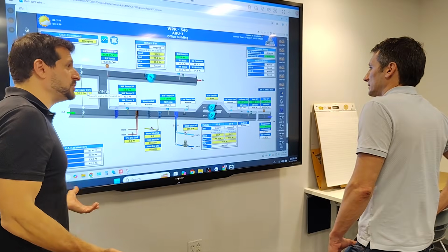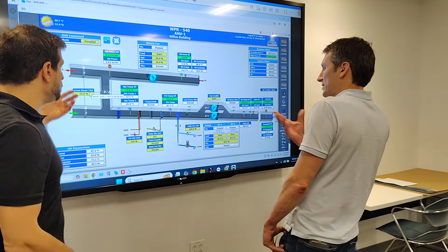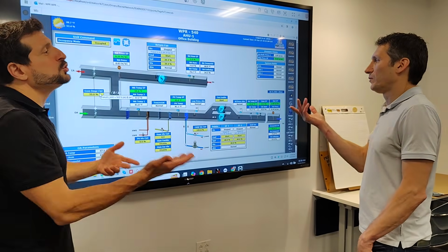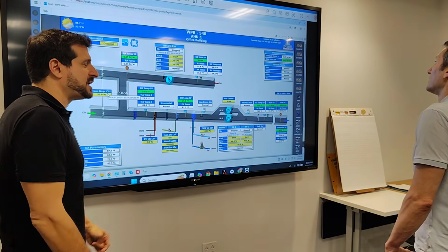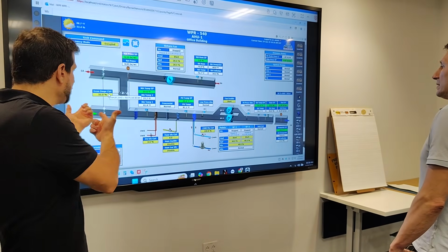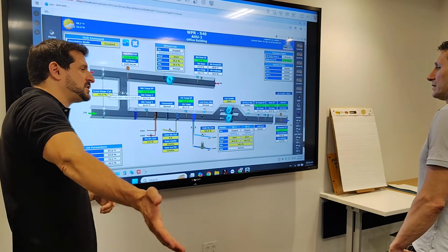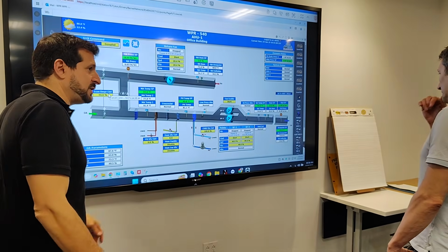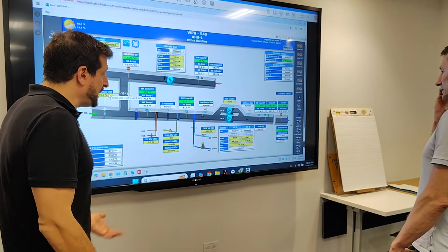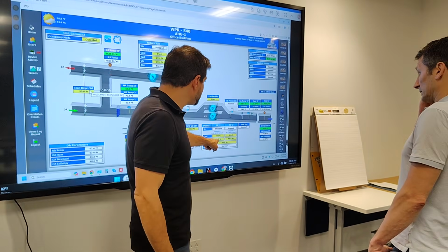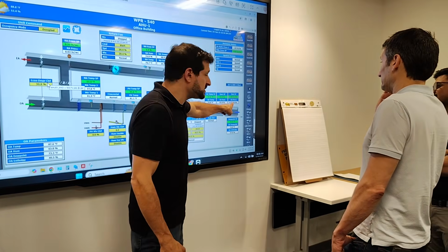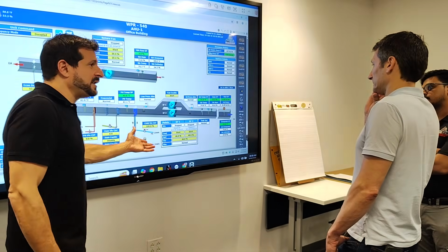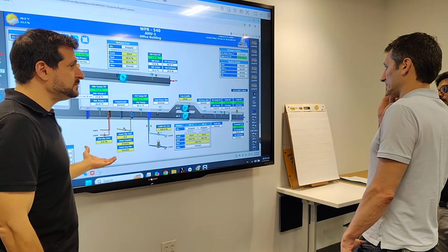You don't have anything initial here, right? But there is something pre-programmed, which you would have to assume is programmed off of those design characteristics. However, the programs that Siemens put in here came way after design, so we don't know what they took into consideration. They might have just thrown in blanket programs. And I'm telling you that watching this for however long we've been watching and seeing this number over here, this is not a tuned system.